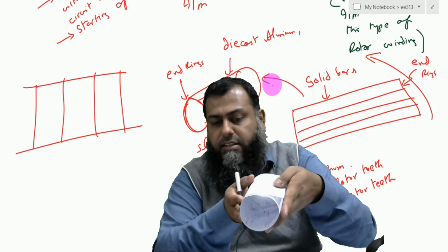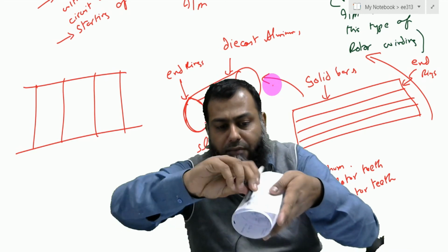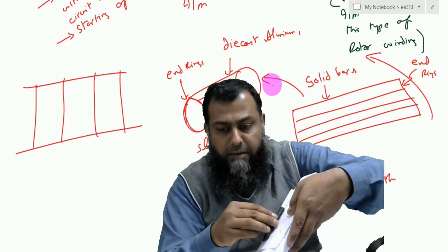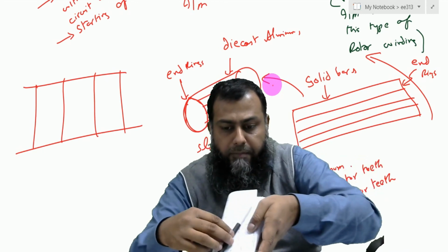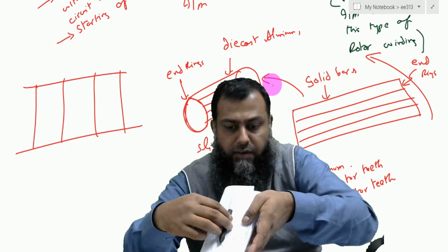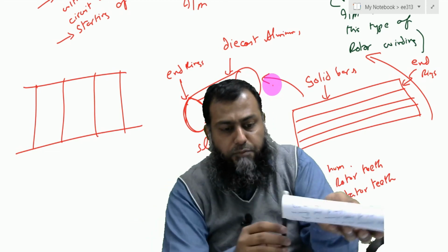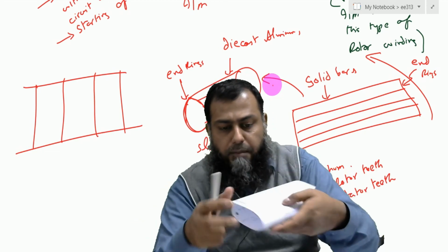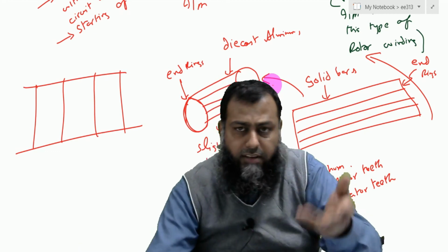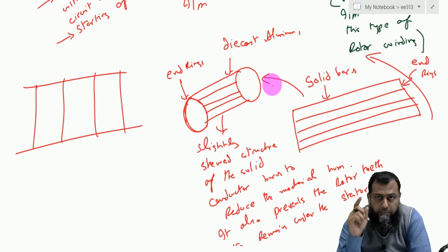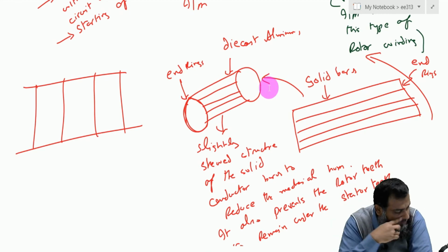it resembles the rotor circuit. Over this we have the conductors, which are not placed exactly parallel with the slots; rather, they are a little bit skewed. So instead of placing them straight, we place them a little bit slanted to reduce the magnetic hum. Both ends are short circuited through a ring. Therefore, if there is a voltage induced in the rotor bars, the immediate action is that there will be a current flow in the rotor circuit as well. So the field is produced by the three-phase current.